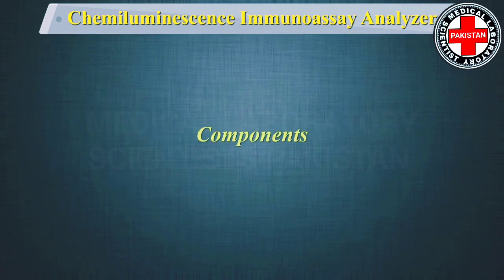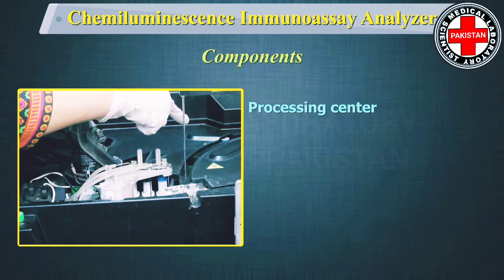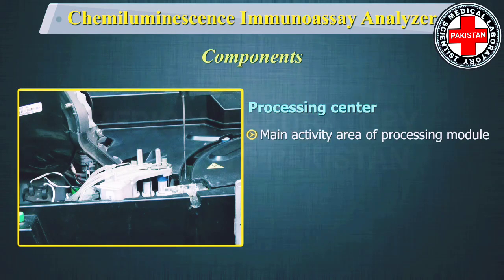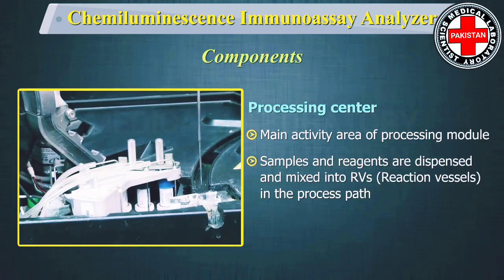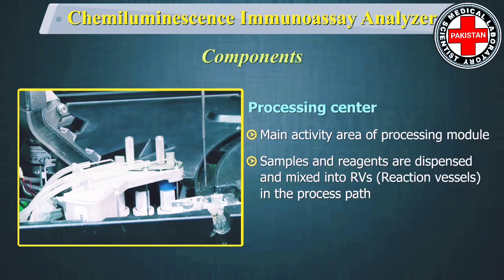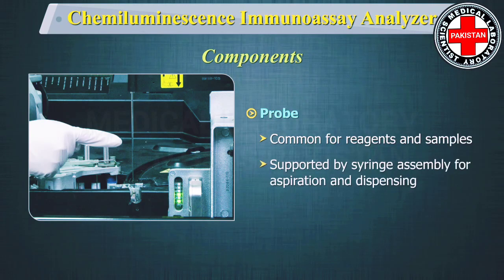Most chemiluminescent immunoassay machines have the following main components. The processing center is the main activity area of the processing module, where samples and reagents are dispensed and mixed into reaction vessels in the process path where assay processing is performed. A probe, which is common for reagents and samples, is supported by the syringe assembly for aspiration and dispensing.